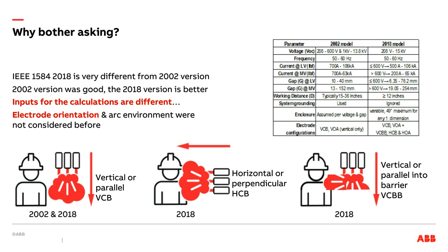But in my experience, talking to people that do studies, I find that most people tend to stick to the values that are in the tables in the IEEE guide, and those values have not changed, the so-called 13, 25, 32, and 40 millimeters. Most people, for low voltage, tend to use those values. In reality, the new model allows you to use different values, but unless somebody's taking a tape measure or knows what those values are, it is improbable that they're changing them for the arc flash study. They may, and some of you who are in the business of arc flash studies may contradict me, because you are following a more thorough or more detailed process than the people that I have seen.